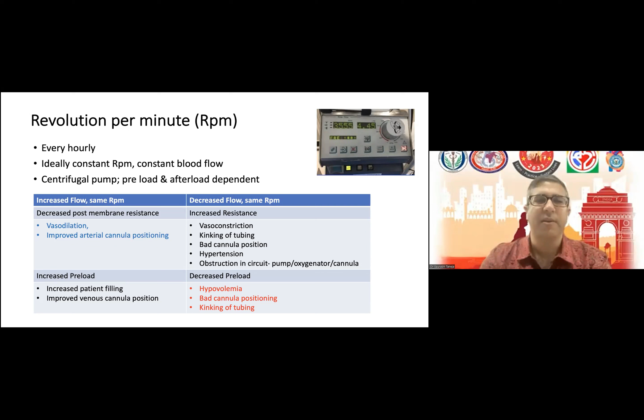If at the same RPM the flow has increased, the arterial cannula may have migrated to a better position, or there is an increased preload by increased patient filling. So you have to correlate the revolutions per minute and the flow and compare it to the previous ones. That is why you need to chart it. The centrifugal pump is a preload and afterload dependent pump, and that is why these changes happen.